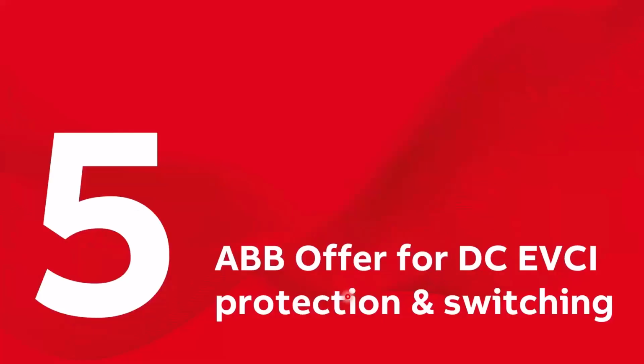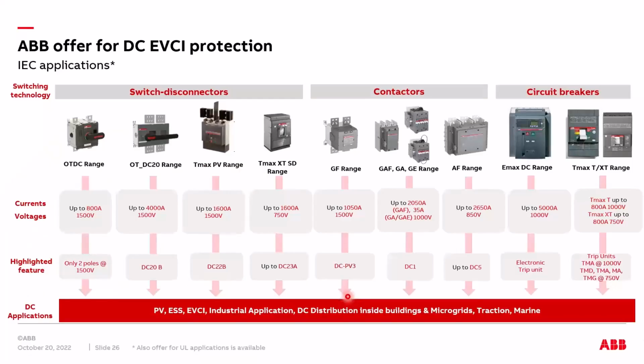So what can we offer as ABB for this type of electric vehicle charging infrastructure? Here, as you can see, and you can go deeper in detail on our website, we have a full range of traditional components, I mean electromechanical components for switching and protection, with the capability to switch the current and to guarantee the galvanic isolation in open position, switch-based and breaker-based. Breaker-based also has the capability of remote tripping, I mean to open and close the switch disconnector by means of a shunt opening release, and to close by a motor operator.